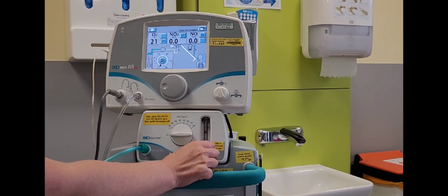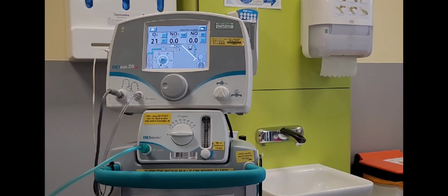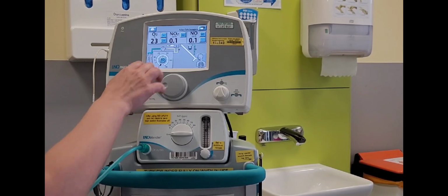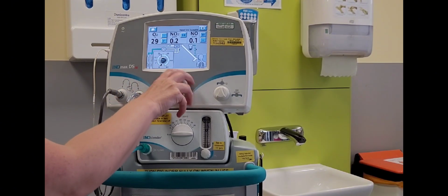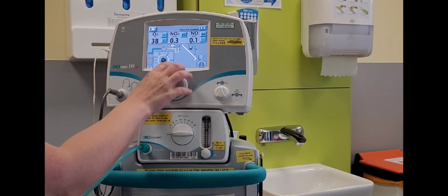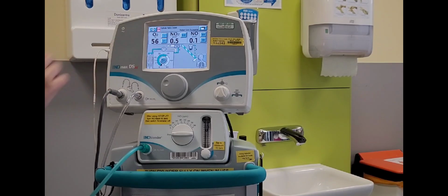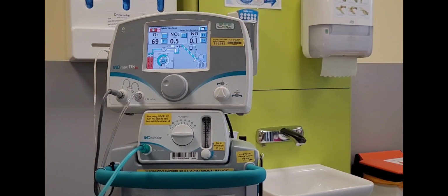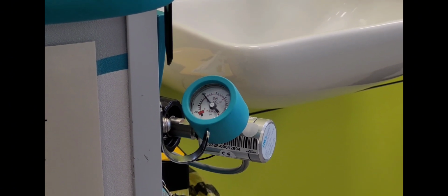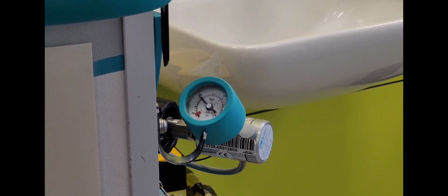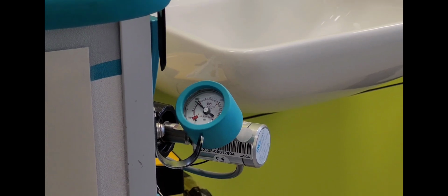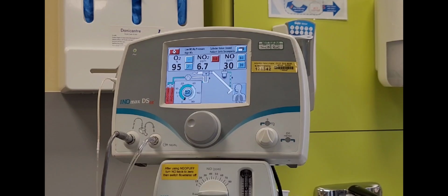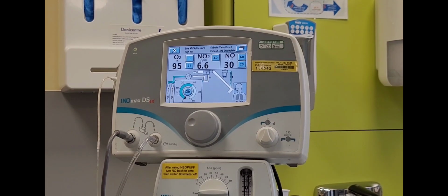The next step is to ensure the nitric cylinders are off and turn your wall oxygen to 10 litres per minute. Set the INOmax dose to 40 parts per million and wait for the cylinder closed valve alarm to appear. The purge will be complete when the low NO alarm appears. The purge is now complete.